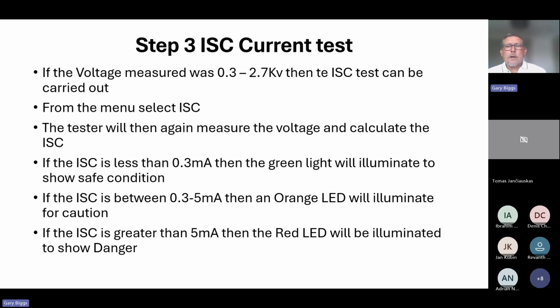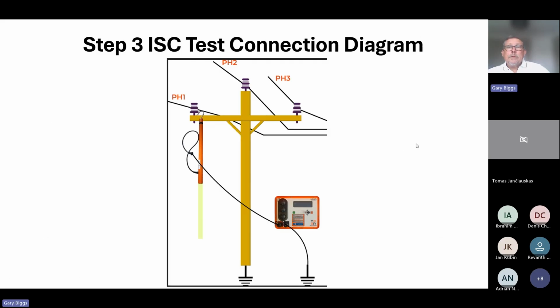As I say, the guys working on 11 kV systems will all be aware of the dangers anyway, and will have the appropriate safety equipment, insulated suits, etc. But this is telling them what level of danger is posed before them on this pole. What we've got here, you can see the way we've connected the instrument is exactly the same as before. You've got the potential there where the poles come down, and we've used that to select the ISC measurement, current measurement, and at the end of the test it will display accordingly.